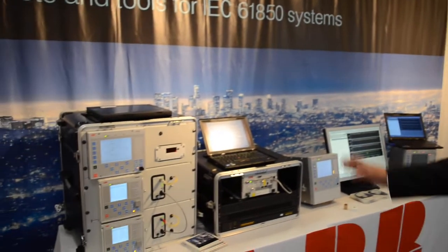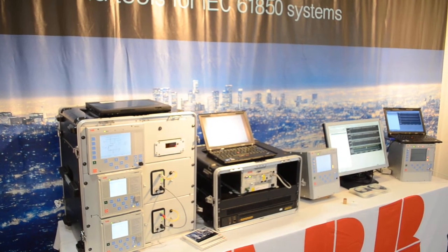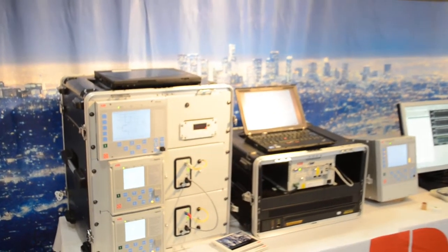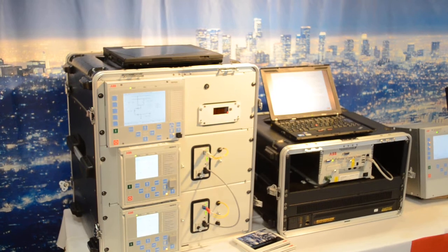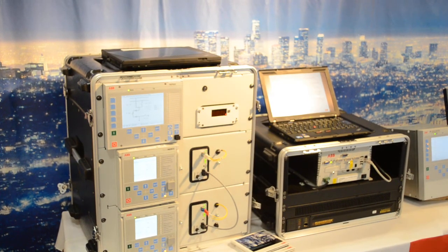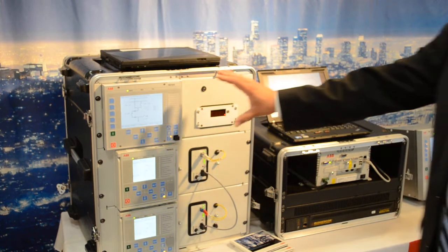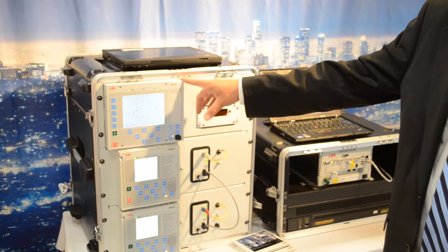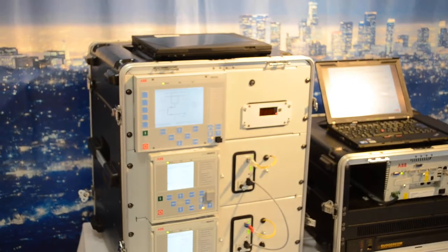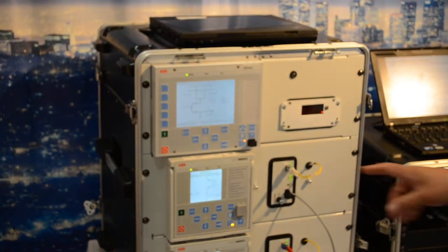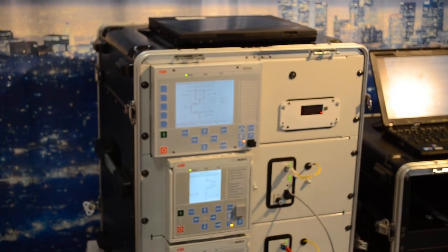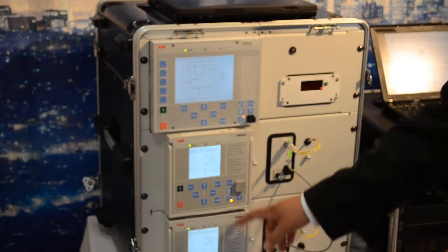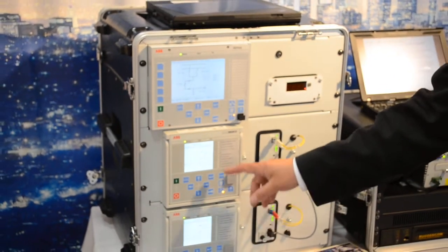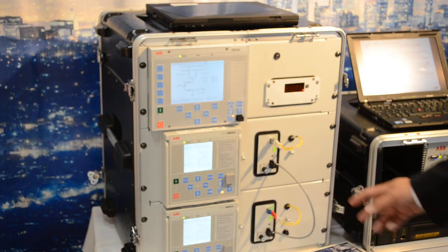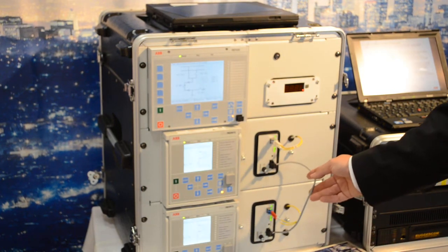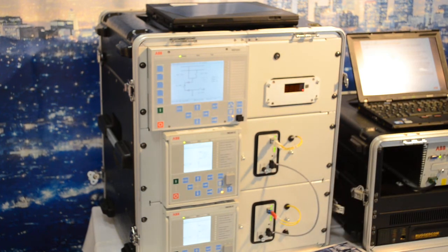On this side of the table, we have a setup demonstrating loss of mains protection using GOOSE and binary signal transfer. The demonstration goes like this: we have an incoming feeder for a main substation, and the REF630 is representing that. Then we have an outgoing line and an outpost generator, let's say a single wind turbine, which is behind a line, and the line is protected with a pair of line differential protection boxes, RED615s. And we are using just normal pilot wire copper cables for the line differential communication.